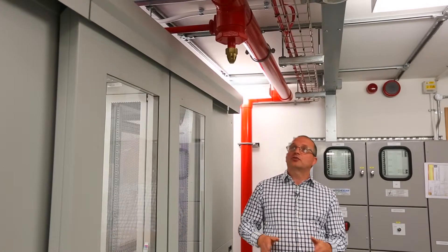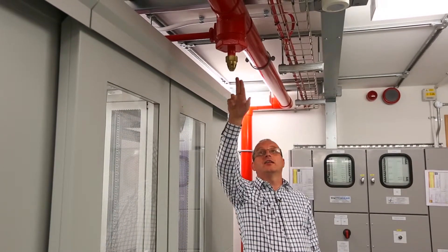Fire is everybody's worst nightmare within a data centre. Here at InTechnology we have a VESDA front end and then a double knock gas release system behind that. The gas we choose to use is a nitrogen-argon mix, which is released by these heads in the event of fire.